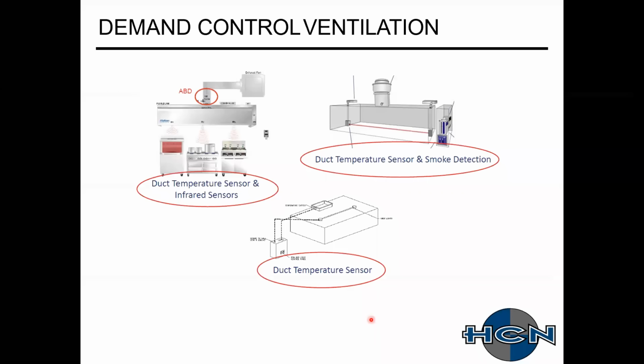Next thing we're going to talk about real quick is some demand control ventilation. There's lots of different products on the market here, depending on if you're using infrared for the types of equipment, or you're using duct temperatures with smoke detection, kind of an optical sensor up in the front of the hood, or your standard just duct temperature, and then a room temperature stat as well.